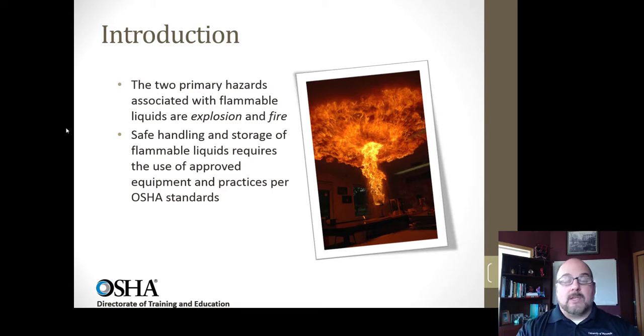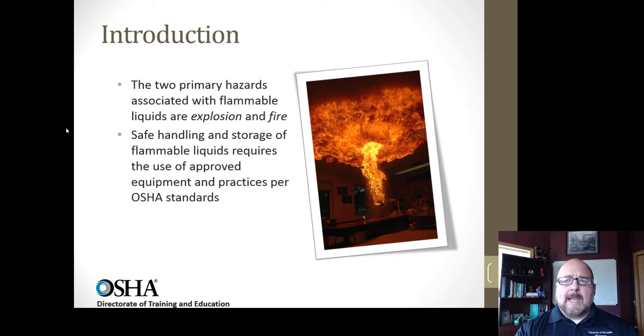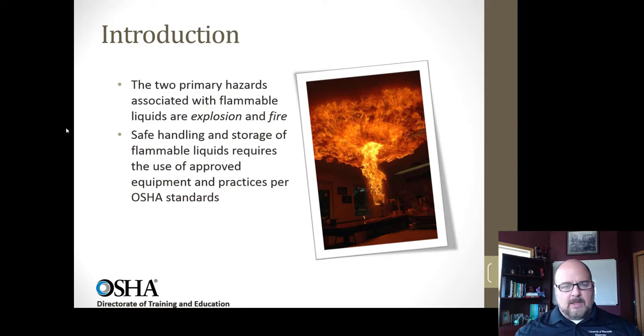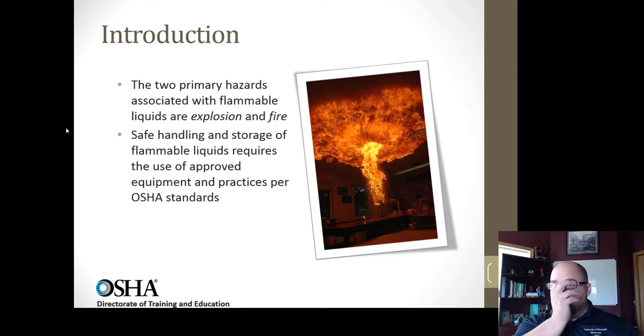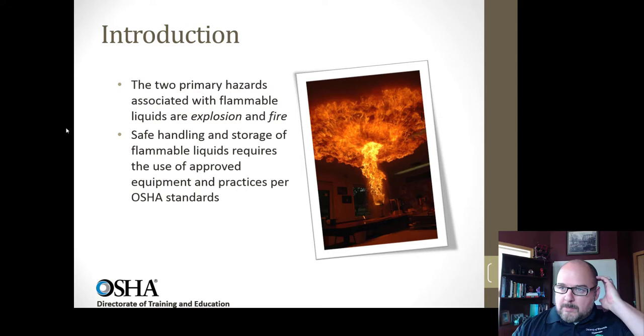We need to properly know what's there — labeling should be number one — then safe handling and storage, making sure it stays within its container because a lot of these flammable liquids are volatile. When a liquid is very volatile, it vaporizes readily in the environment when not contained, because it's the vapor that burns, not the liquid. The liquid's natural capability to become vaporized and be within a concentration between the lower explosive limit and the upper explosive limit dictates whether it's ignitable, able to burn, and possibly explode.